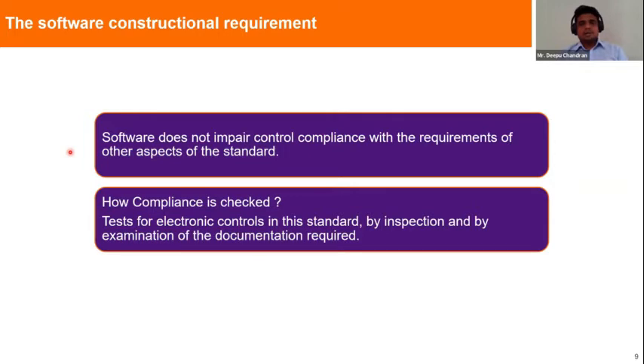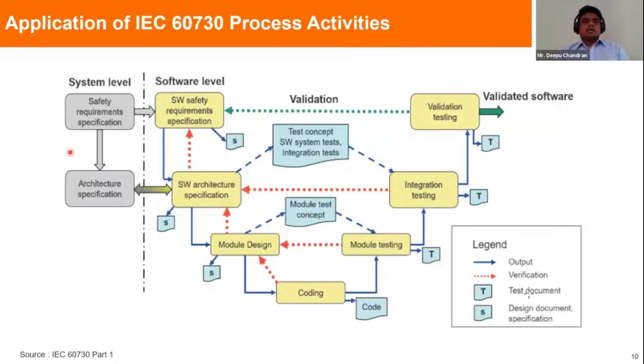And how do we verify this compliance? The standard also talks about the verification techniques. Tests can be done for electronic controls according to the standard document, and you can do it by performing an inspection or by examining the specification with respect to the documented evidence that is required from the standard process point of view. So I'm directly taking you to the process activities according to IEC 60730 for constructing the software. You can see here that the technical safety requirements are given as an input to the software lifecycle along with the hardware software interface specification.